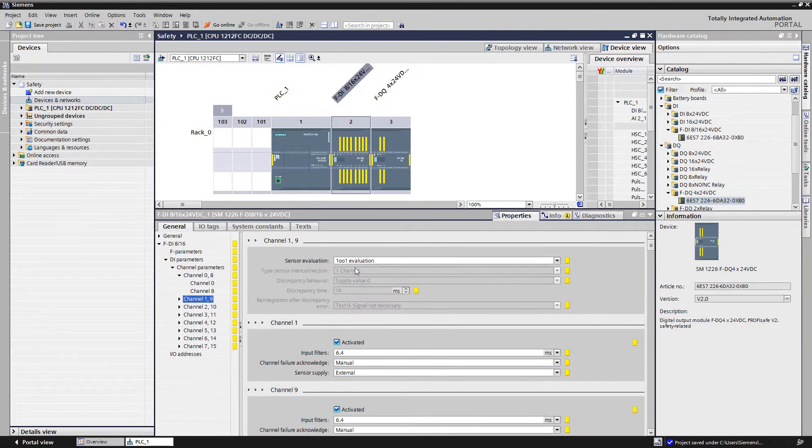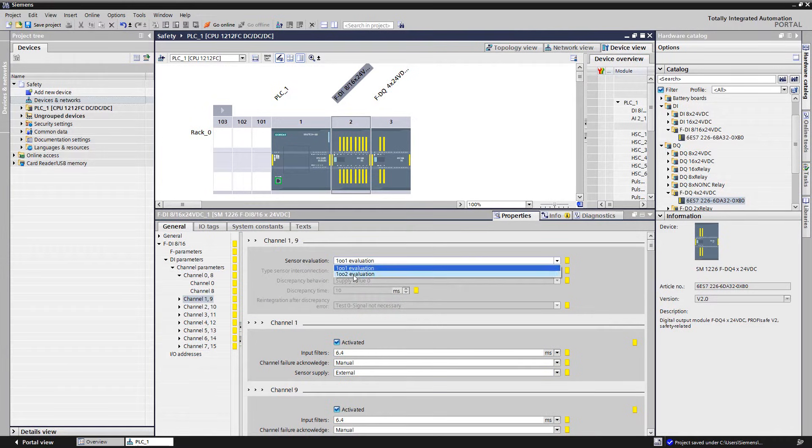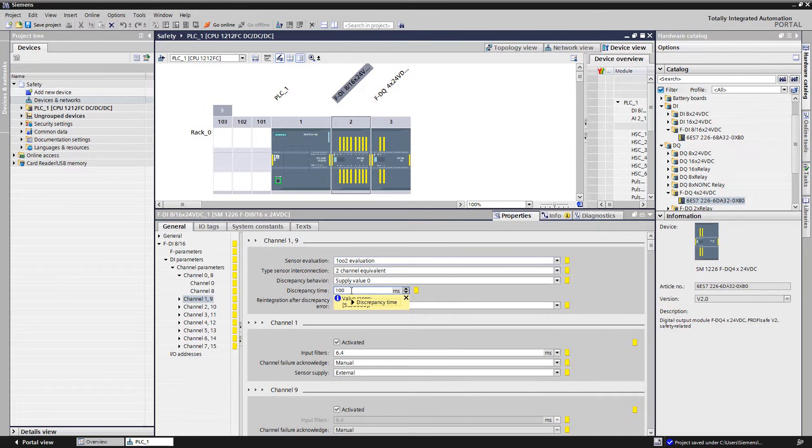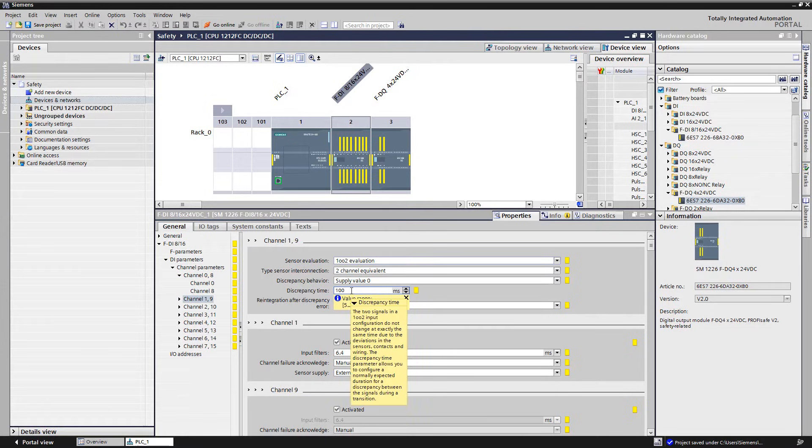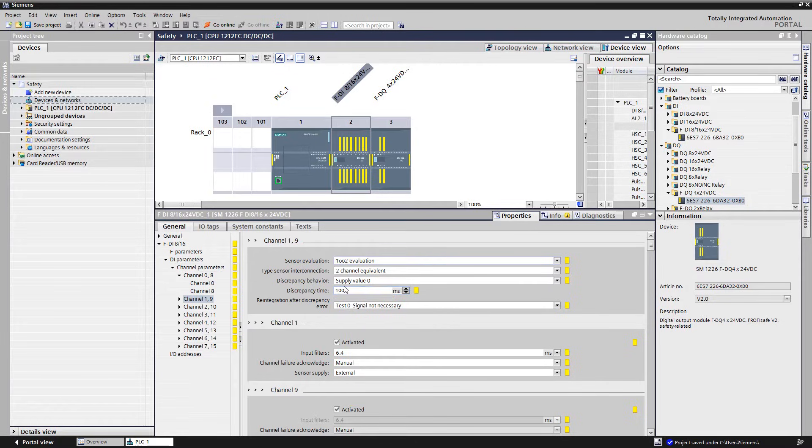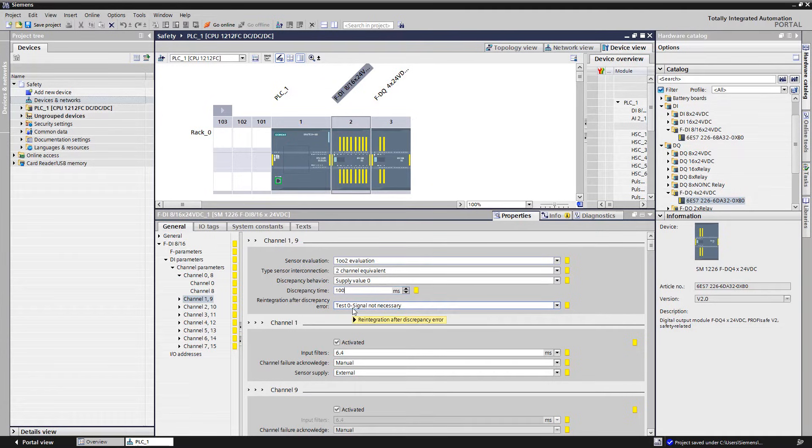For the evaluation of the RFID positioning switch of the safety door, we also select a two channel evaluation 1 out of 2. We increase the discrepancy time to 100 milliseconds and keep the encoder supply on external. The sensor already provides a safe signal with sensor integrated diagnosis and therefore does not require a monitored supply from the module.